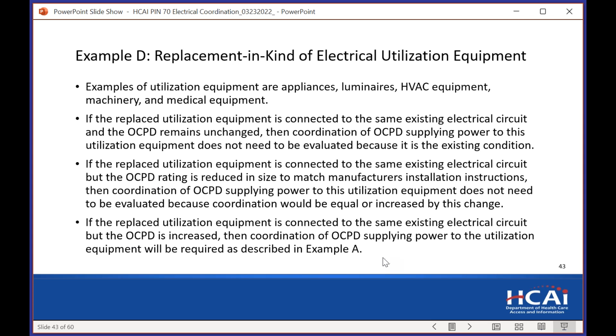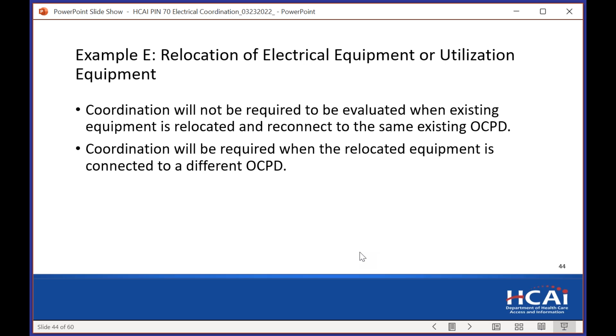Relocation, here it is. I think Mike had a question on this. Relocation of electrical equipment or utilization equipment. Coordination will not be required to be evaluated when existing equipment is relocated and reconnected to the same OCPD. So you're moving a panel because it's in the wrong location. You do not have to demonstrate coordination. And that aligns with the remodel can.